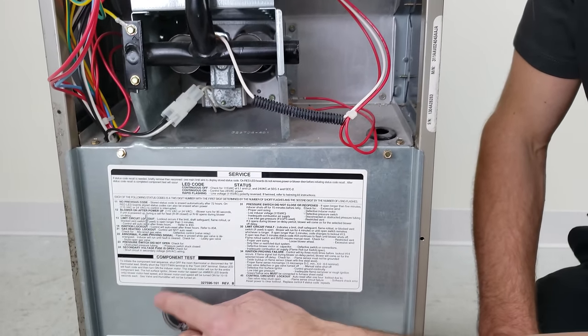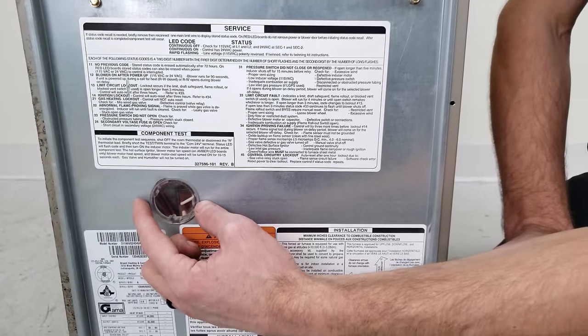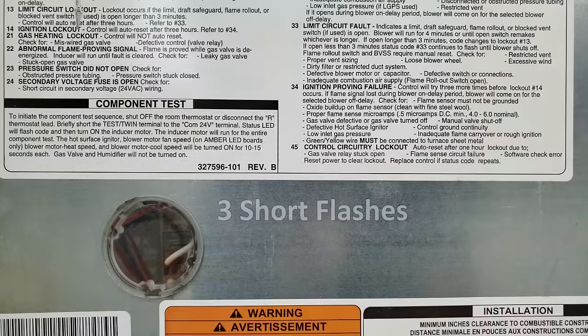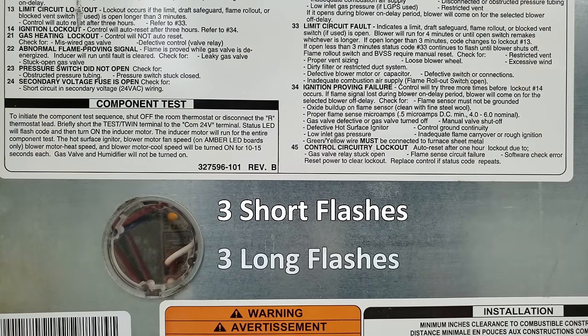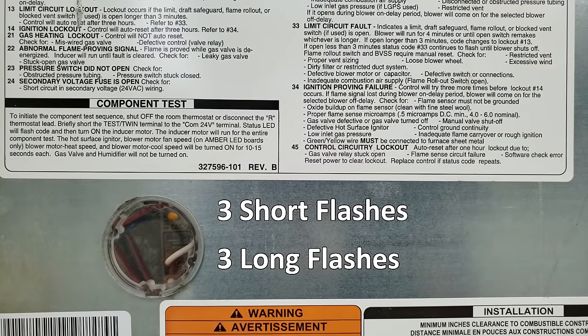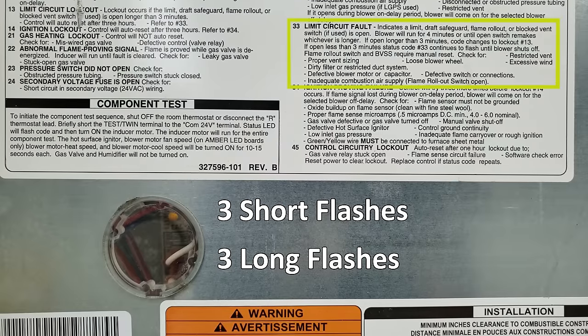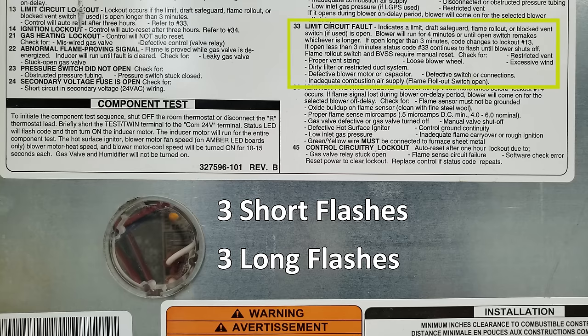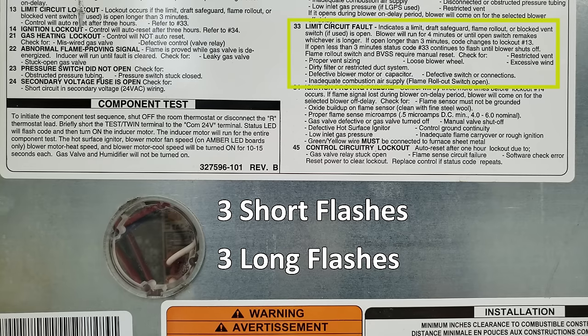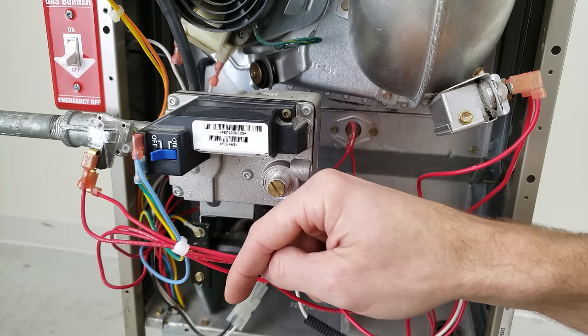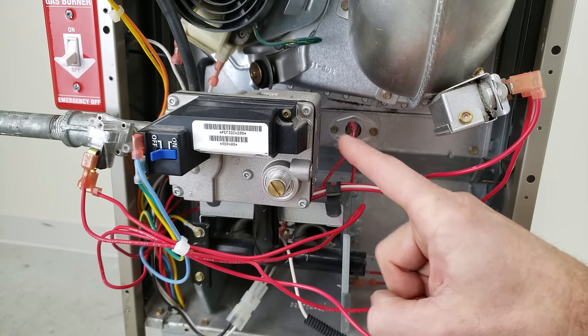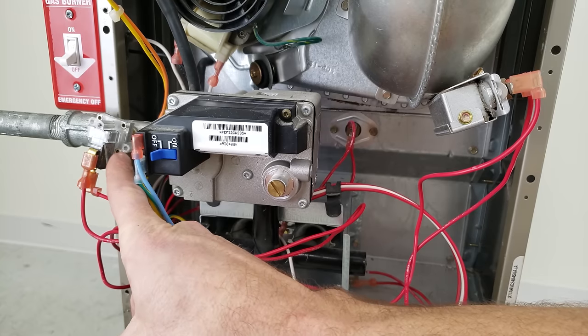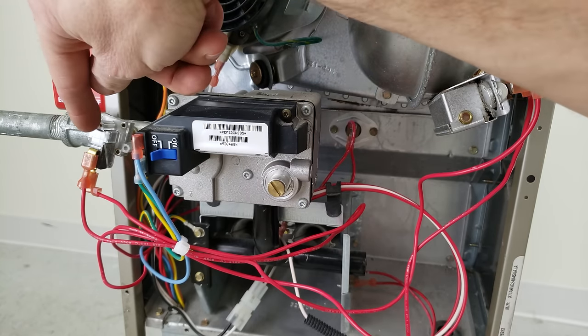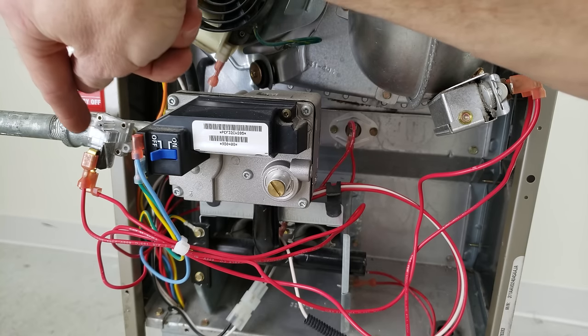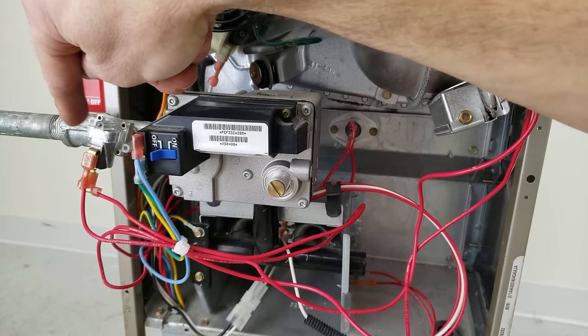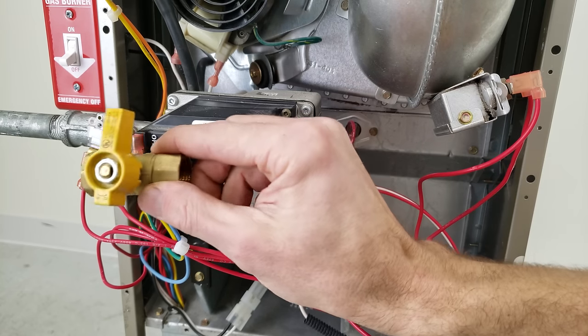And so what you want to do is look down here in this hole and take a look at the LED status code light for the error code. Even if the error code is signifying that one of these switches is the problem, you could also have a low pressure LP gas switch installed. So this is in the case of a propane gas furnace, and this would open up the electrical circuit if the propane tank is low on gas or if the gas valve is turned off.